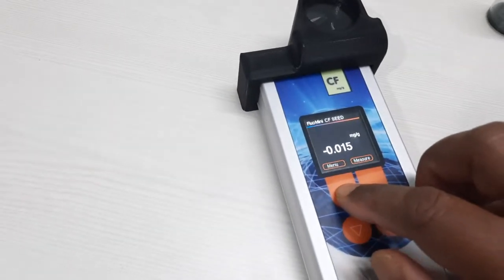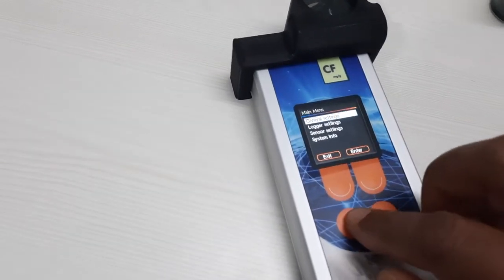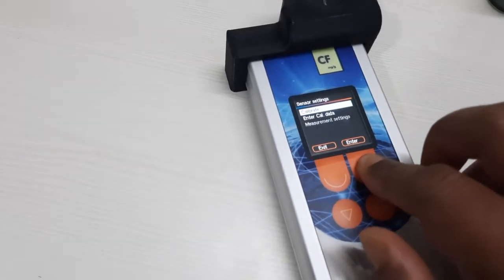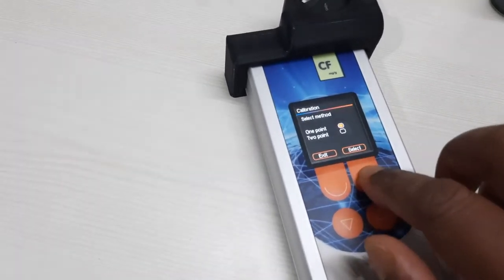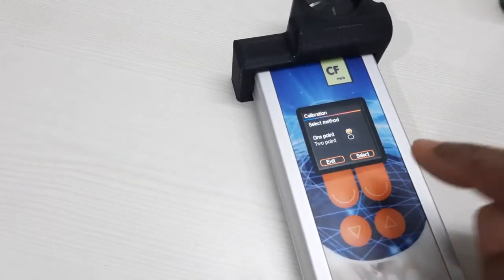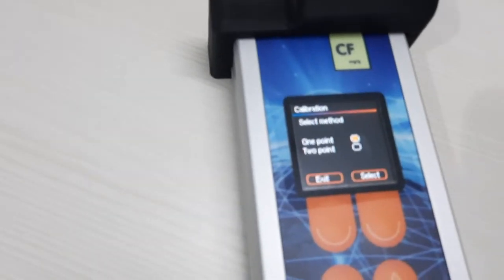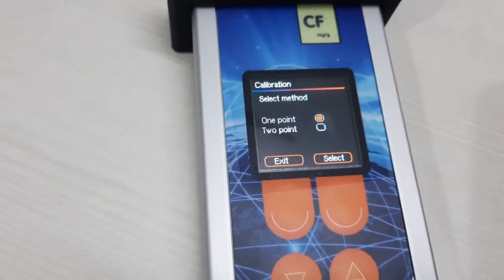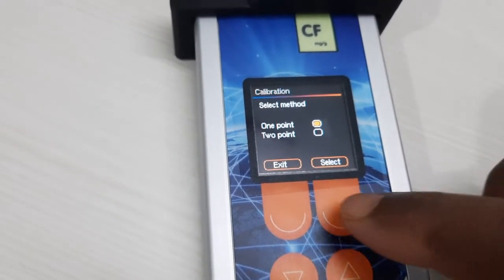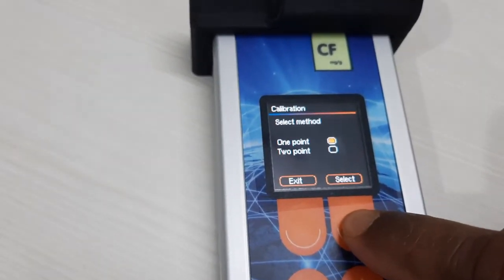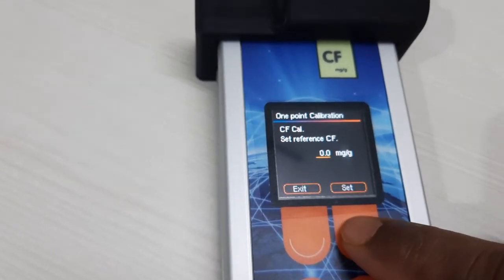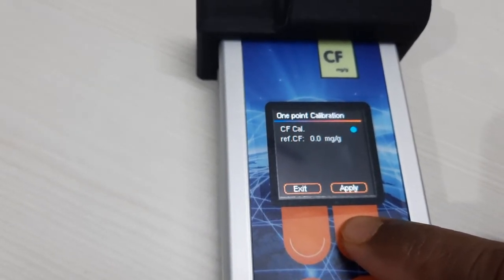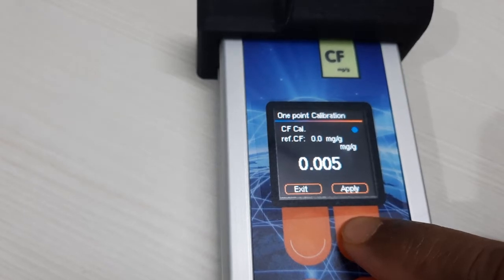So moving to menu, go to the sensor setting, enter calibrate. Let us start. There will be two types of calibration: one would be the 1 point calibration, and one would be the 2 point calibration. So if we select 1 point calibration, you can set it at 0 because we want it to be 0, and it will do a continuous measurement through the sensors.